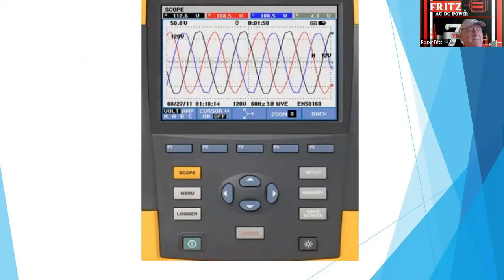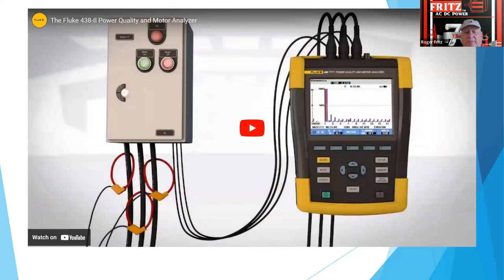We use the Fluke 434 meter to do some determinations on bigger applications before we get involved, so that we can come in and sense what the power quality is. It literally reads the waves that show the 60 cycle power, and reads the voltage line to line and line to neutral, so we get the full spectrum. It shows us our imbalances, our noise, and any existing harmonics that could be coming from the power line. We'd like to take a view of where we are to begin with. I'm going to run this. This is a little bit about why I don't sell Fluke meters, but we really swear by them.